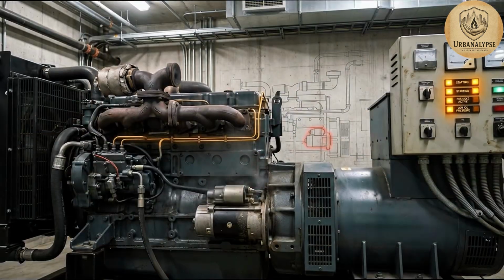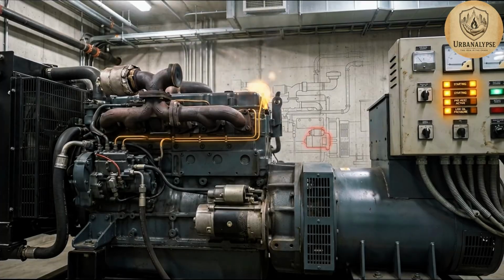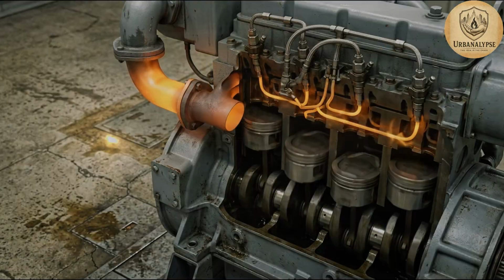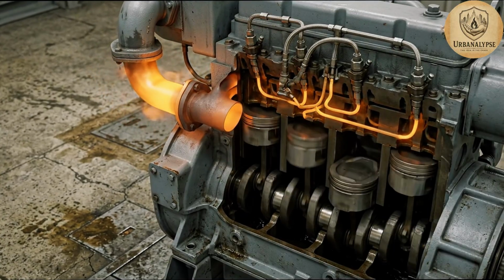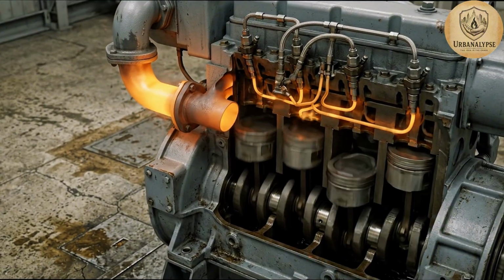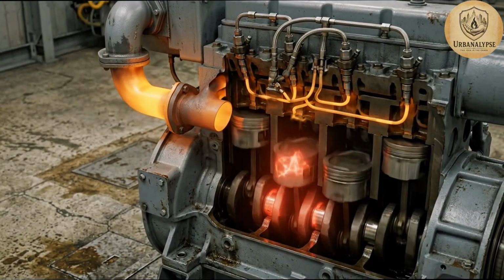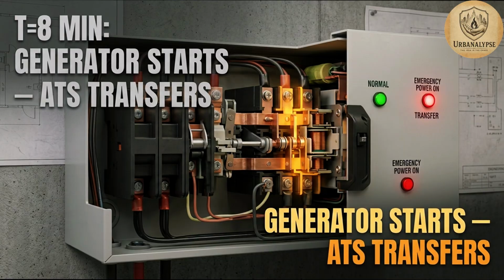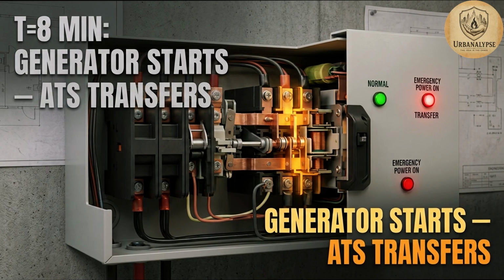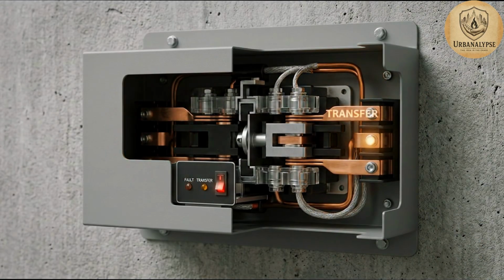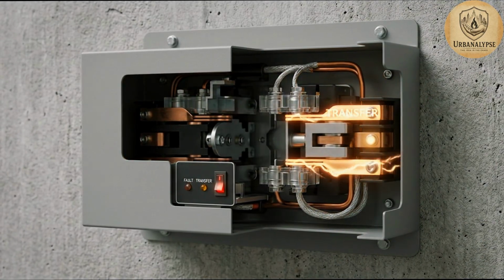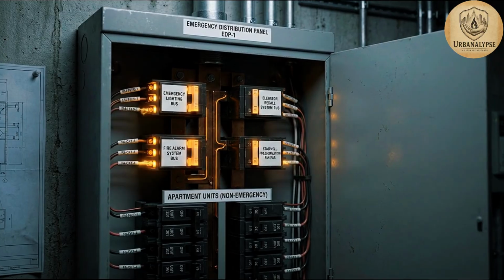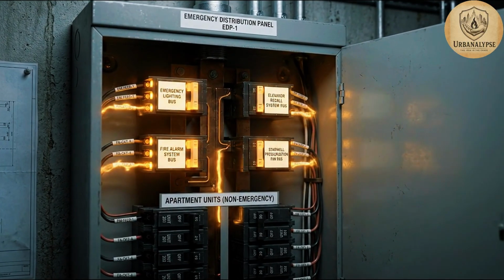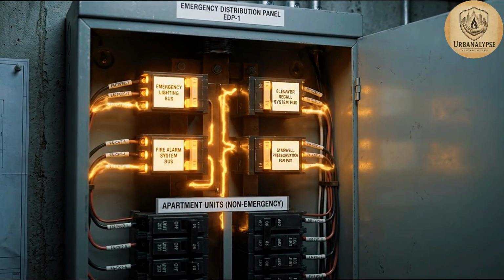The building's internal climate depends on that thermal mass because at T8 minutes onward, the generator, if the building has one installed on site, starts and the automatic transfer switch, or ATS, closes onto the emergency bus, feeding only a pre-selected list of circuits defined at commissioning. Most residents assume that moment restores power to their apartment. It does not, and this is the reveal that separates residents who understand their building's wiring from residents who simply occupy space inside it.